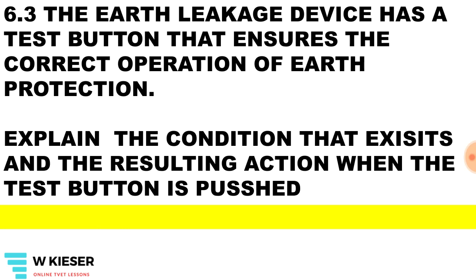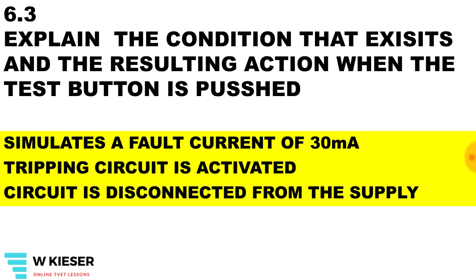The earth leakage device has a test button that ensures the correct operation of earth protection. Explain the condition that exists and the resulting action when the test button is pushed. It simulates a fault current of 30 milliamps, it will cause the tripping circuit to be activated, and the circuit will be disconnected from the supply.